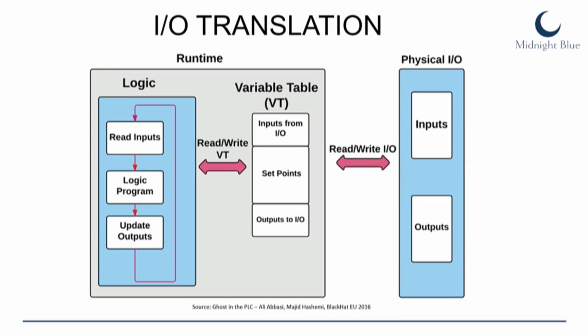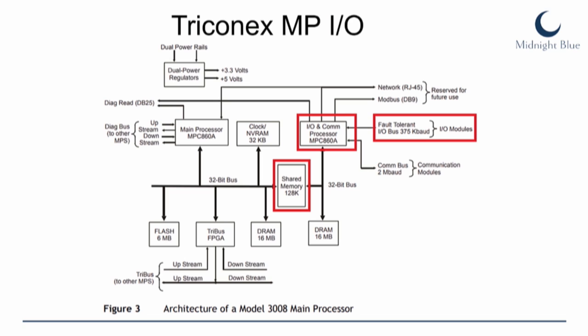Now, internally, this looks like this on these devices. You have the physical I/O, you have the logic, and there is an intermediary variable table that manages this. On the Triconex, this is handled by an I/O processor that has a shared memory connection to the main microcontroller, and that's where it places this variable table.